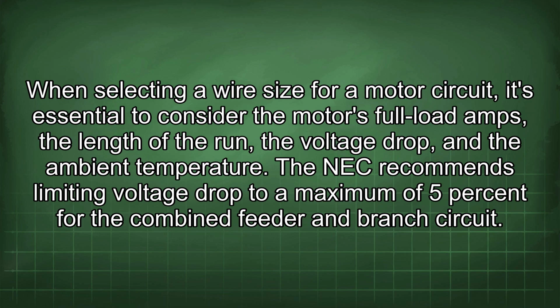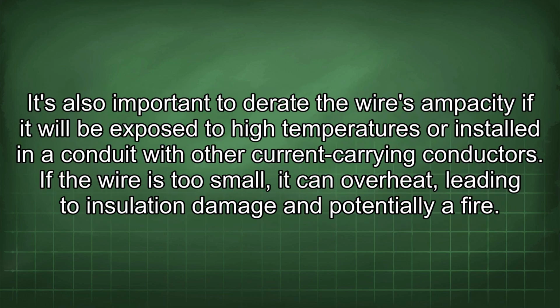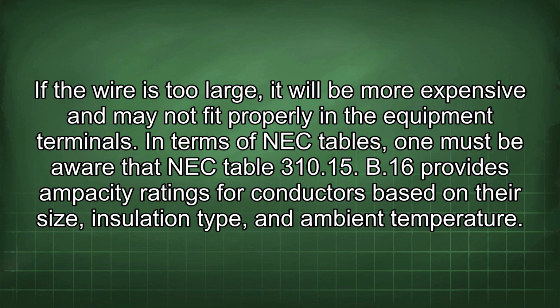The NEC recommends limiting voltage drop to a maximum of 5% for the combined feeder and branch circuit. It's also important to derate the wire's ampacity if it will be exposed to high temperatures or installed in a conduit with other current-carrying conductors. If the wire is too small, it can overheat, leading to insulation damage and potentially a fire. If the wire is too large, it will be more expensive and may not fit properly in the equipment terminals.